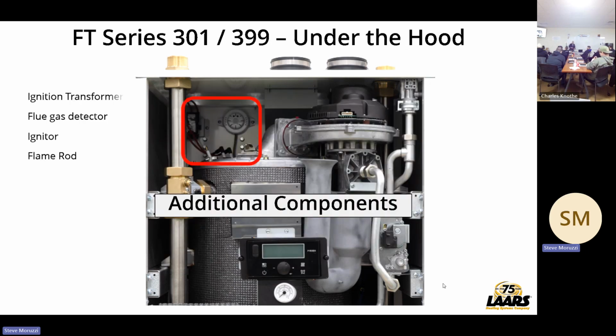And by the way, if you look, that tees, so I can go up and do a top connect piping for supply to the building, or bottom, or both. My example before, if I want to feed heat out to the building, maybe off the top of the boiler, and then the indirect off the bottom, I can.